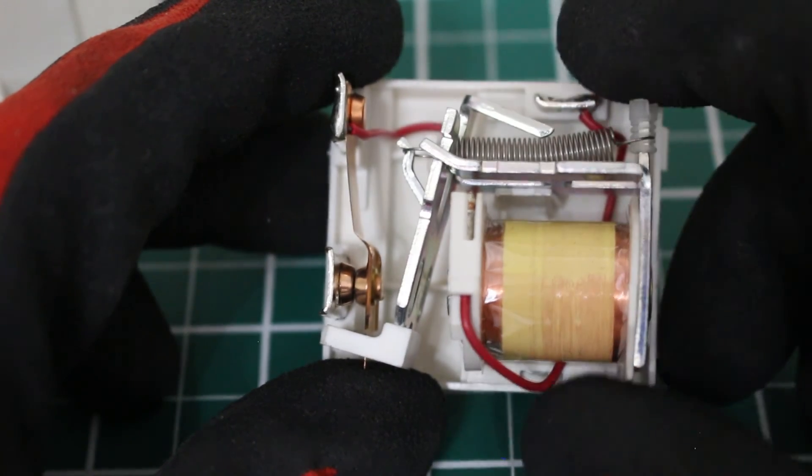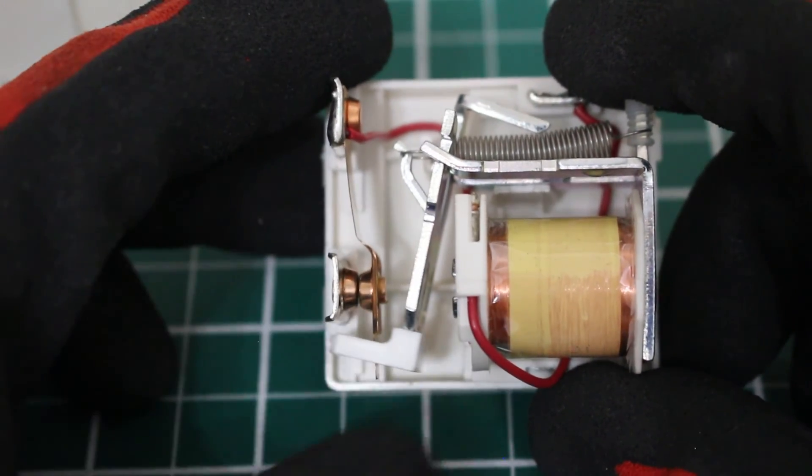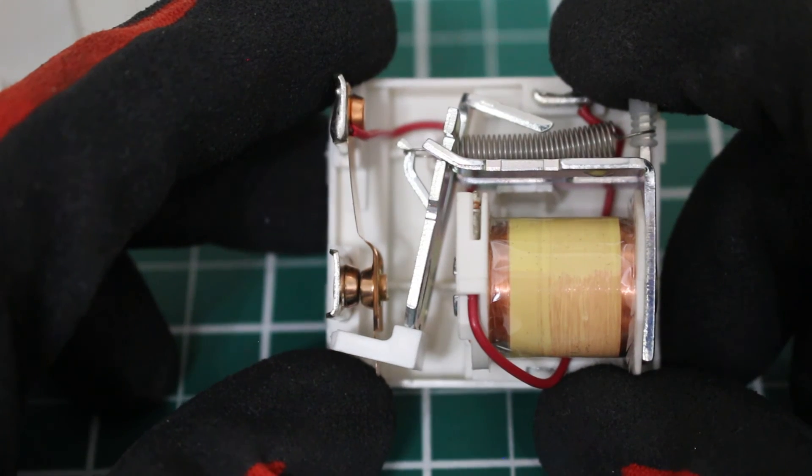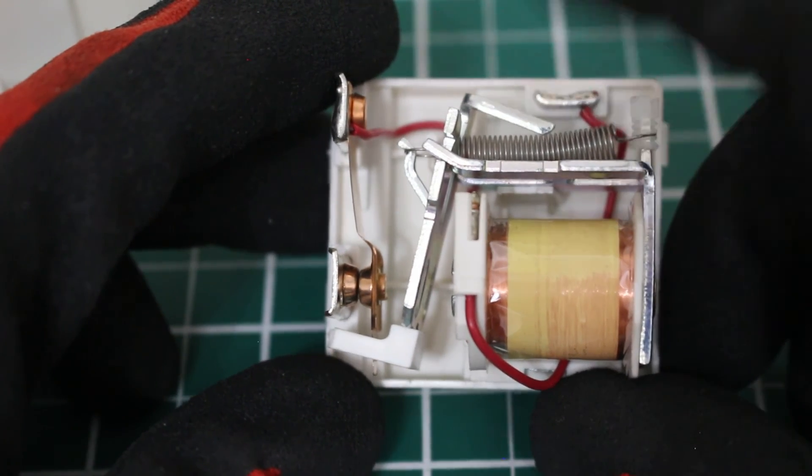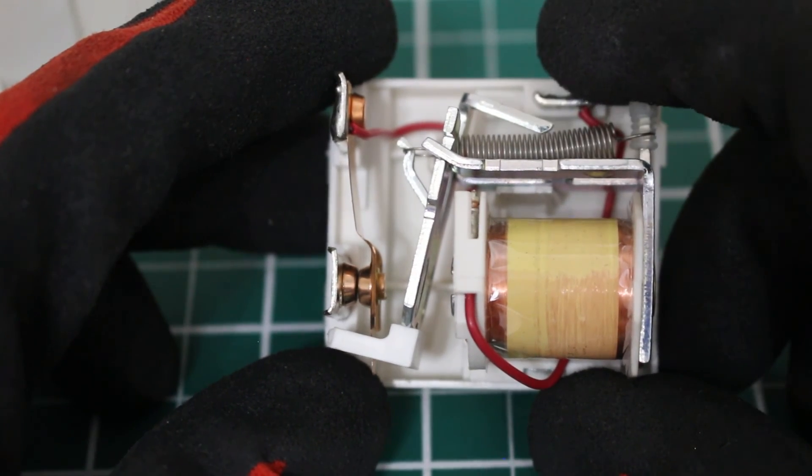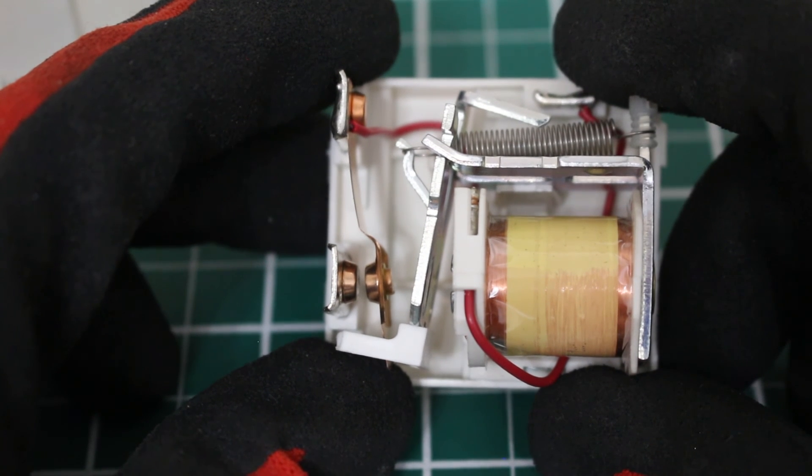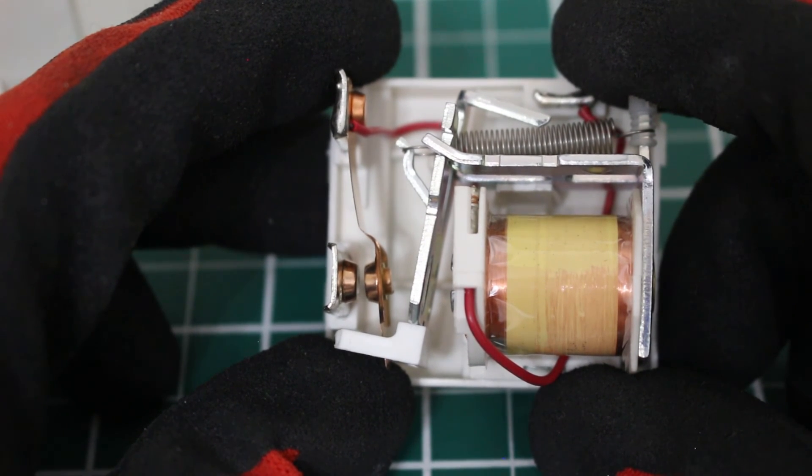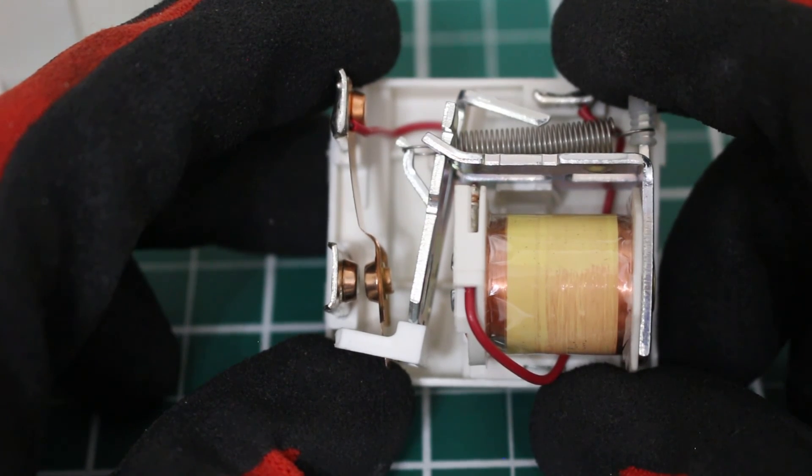So, power is going to come in, go through, start our motor, run through the run cap. Once that back EMF overcomes the force of this spring, we're going to open our contacts and we're going to remove power from our start cap. And the compressor continues to run.